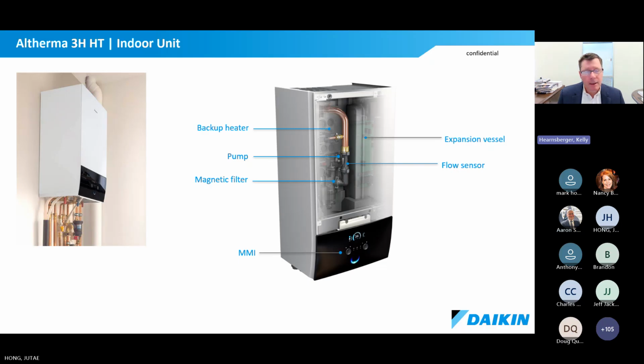There's an expansion vessel built in. Also, the backup heater. And what I didn't mention before is if there was a situation where the outdoor unit needed a maintenance call, or something took the outdoor unit out of play in the system, the backup heater is a 6 kW backup heater inside the head unit. And so it could serve the heating and the hot water space adequately until that outdoor unit can be serviced. It does not have to be wired directly into its own breaker. It could be in a shared breaker with a car charger in your design build environment. So there's a lot of unique ways you can operate the system breaker-wise as well. Next slide.